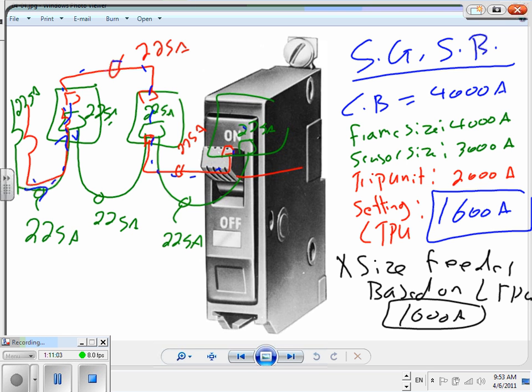With the plug-in, I can change this one to 3,000 amps and the setting to 1, which makes this 1,600 amp circuit breaker a 3,000 amp circuit breaker in literally 1 minute. I unplug the trip unit here, and I have another trip unit that plugs right into a 3,000 amp plug unit, and with a screwdriver I turn the setting from 0.8 all the way to 1. Now I can change this 1,600 amp circuit breaker into a 3,000 amp circuit breaker within a minute.